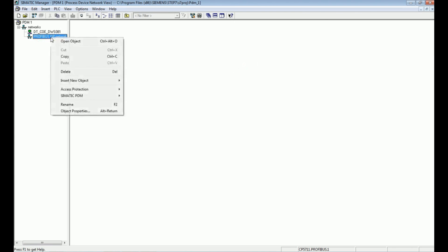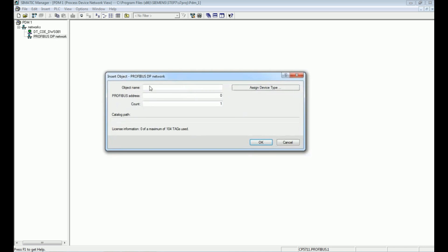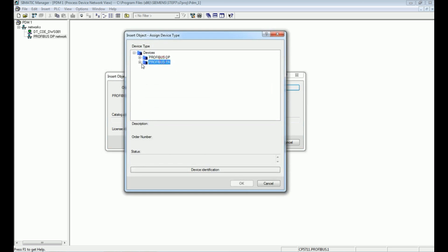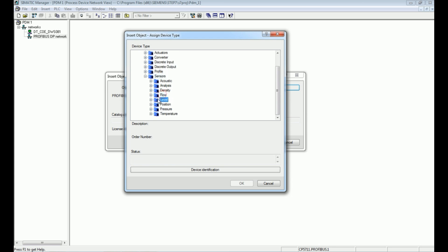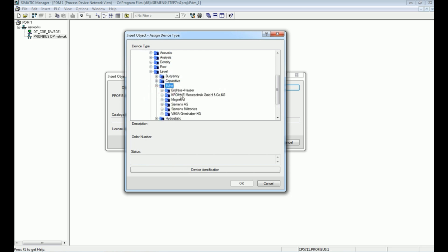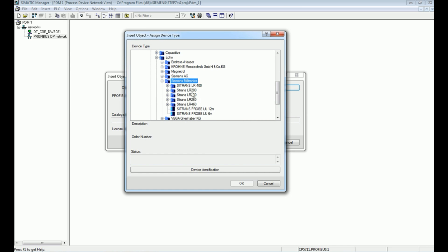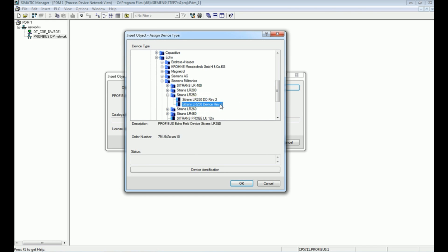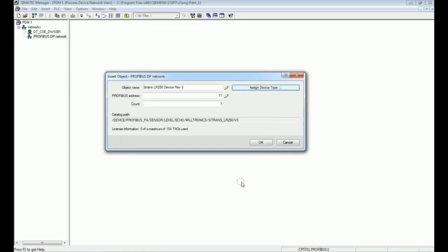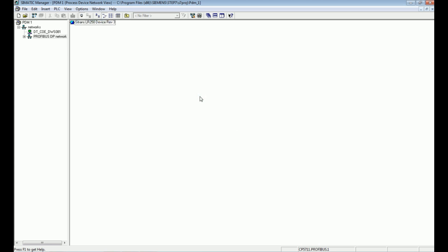Now we will add the LR250 device to the Profibus DP network. Go to Network and Object View, add Profibus address 11 for the LR250, and go to 'Assign Device Type'. The LR250 device is connected with Profibus PA cable. Select Sensor → Level → Radar → Echo. The manufacturer is Siemens Milltronics and the model is LR250. We are given two versions — select the latest LR250 model and press OK. The LR250 device has been successfully added.